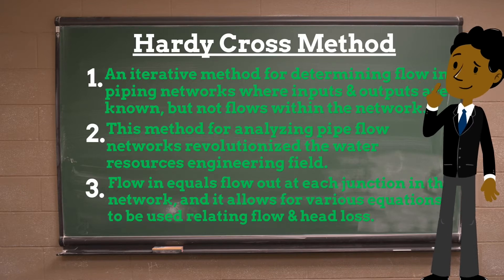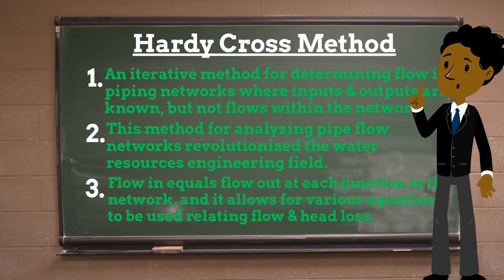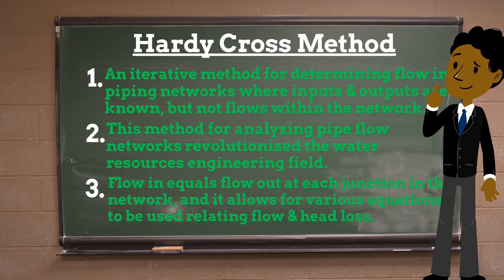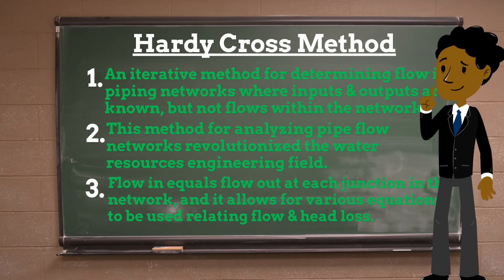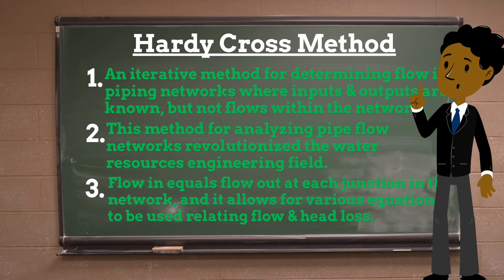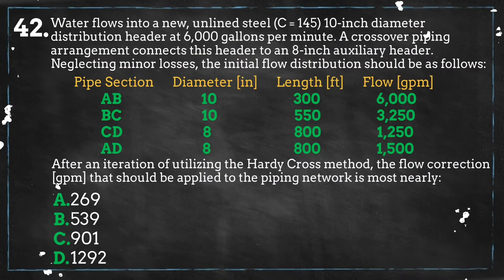The Hardy Cross method assumes that the flow going in and out of the system is known, and that the pipe length, diameter, roughness, and other key characteristics are also known or can be assumed. The method also assumes that the relationship between flow rate and head loss is known, but does not require any particular relation to be used. In the case of water flow through pipes, a number of methods have been developed to determine the relationship between head loss and flow, and the Hardy Cross method allows for any of these relationships to be used.